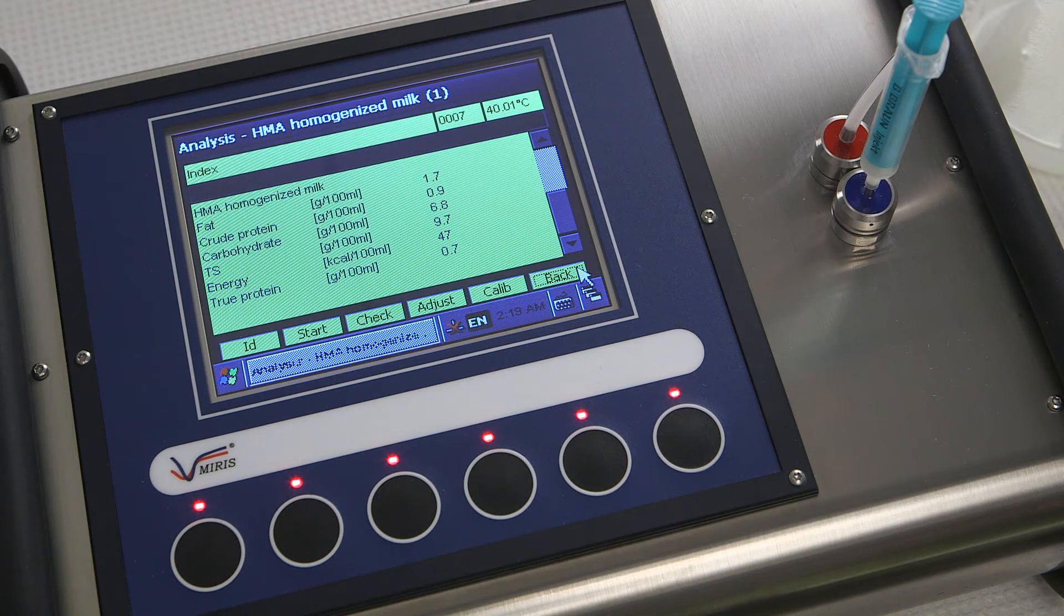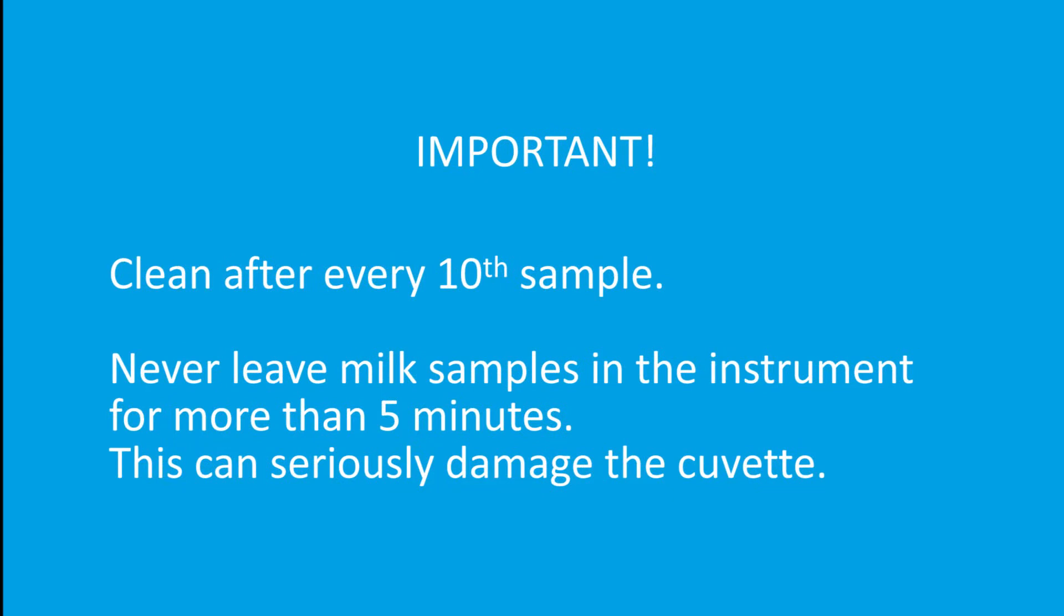Up to ten samples can be analyzed in a row. During analysis, remember to clean after every tenth sample and never leave samples or cleaning solution in the instrument for more than five minutes, as this can seriously damage the cuvette.